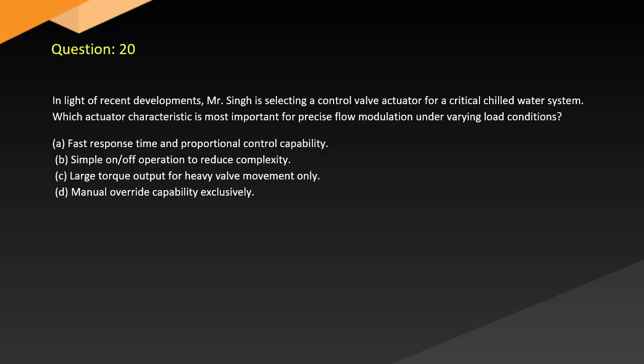Question 20. In light of recent developments, Mr. Singh is selecting a control valve actuator for a critical chilled water system. Which actuator characteristic is most important for precise flow modulation under varying load conditions? A. Fast response time and proportional control capability. B. Simple on-off operation to reduce complexity. C. Large torque output for heavy valve movement only. D. Manual override capability exclusively.